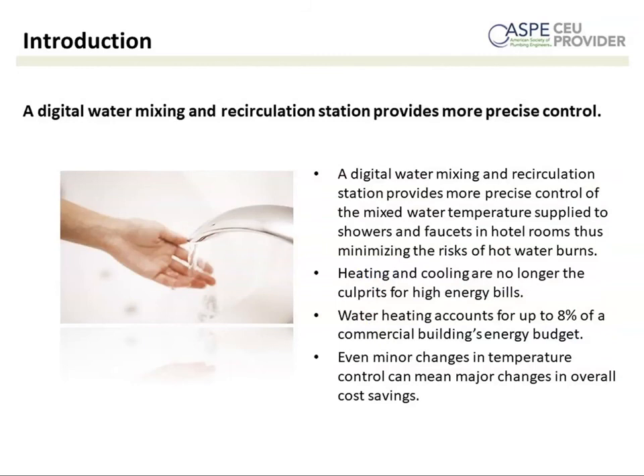So digital water mixing and recirculations, again, provide more precise temperature control. We talked about that. And if you weren't aware, water heating accounts for about 8% of a commercial building's energy budget. I've seen numbers fluctuate between 6 and 10, but roughly about 8%. So it still is significant. And again, even small changes in temperature, the ability to control temperature, can result in fairly large costs over time. So it's not to be underestimated.